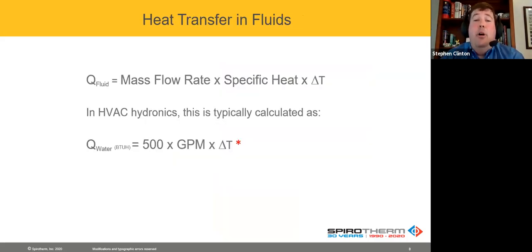All right. My boss likes to say that I can be a real geek. So I'm going to go geek mode on everybody. Basically, we're going to go back to heat transfer. And we're going to look at that. When you calculate that, that's the mass flow rate of the fluid times the specific heat of the fluid times the temperature differential. In our industry, we've kind of done that down to, the rule of thumb is 500 times the gallons per minute of flow times the temperature differential. Where that comes out to is that's basically 1 gallon of water with a 1 degree temperature differential, about 499.8.